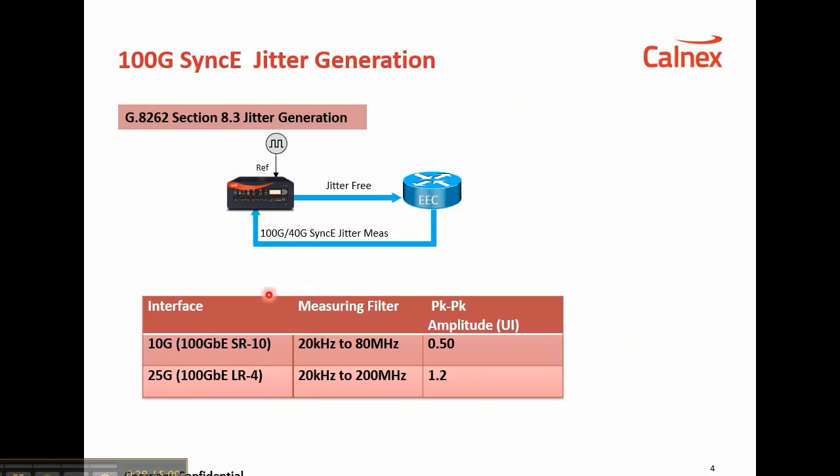This is a test setup for a jitter generation measurement. You need to apply a jitter-free stimulus — this could be the Paragon 100G with the jitter switched off — and jitter measurement is performed on port 2 of the Paragon 100G.